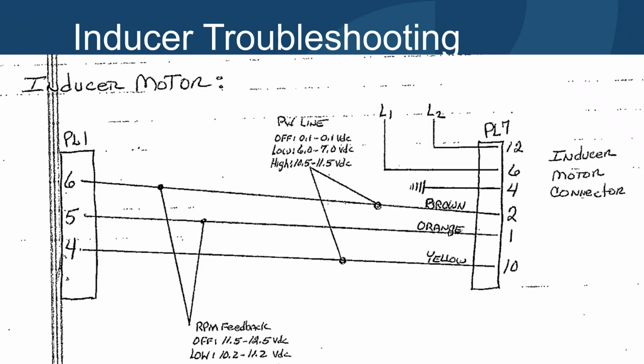An ECM inducer motor will have high voltage supplied to it at all times. Then you will have control wires that go to the motor that will give it the signal to run. In this example, we have a pulse width line, which has DC voltage supplied to it for low and high speed. We also have an RPM feedback line, which feeds back to the control board and tells it that the inducer motor is running. So when you're checking ECM motors, you need to have these voltages so you know how to troubleshoot the ECM motor.